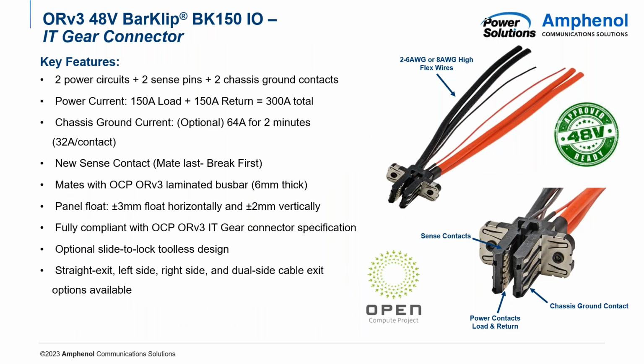So I'll first start with the BK150. The BK150 is the IT gear connector spec rated at 48 volts. This connector is rated up to 150 amps load and return, so we did increase the power density from ORV2 from 100 to 150 amps. This 150 amps is rated in still air.